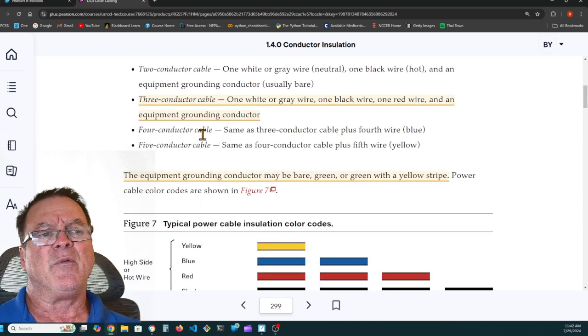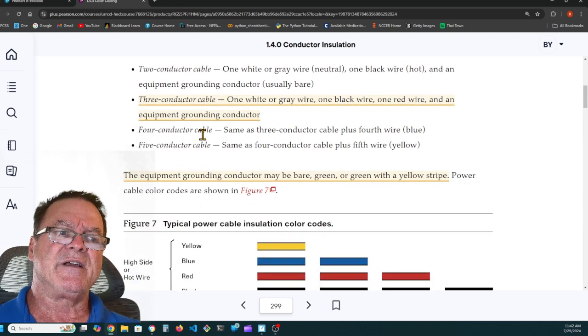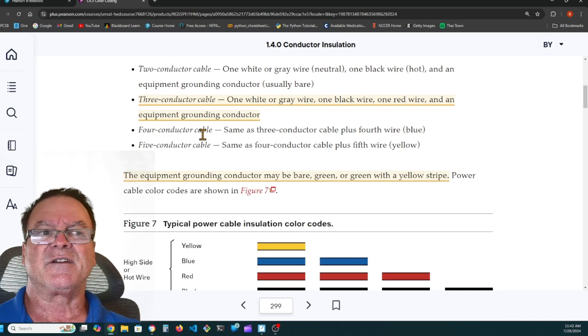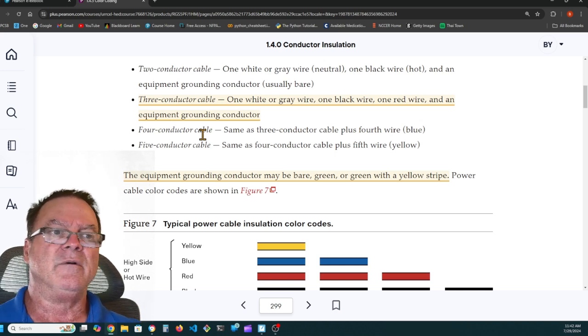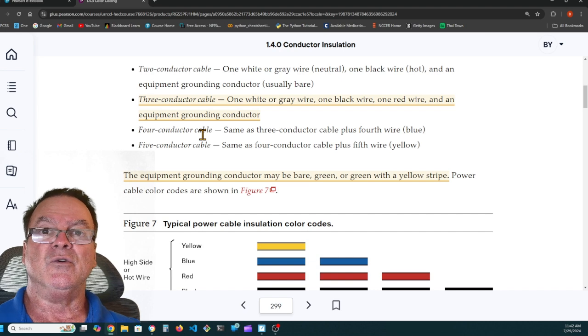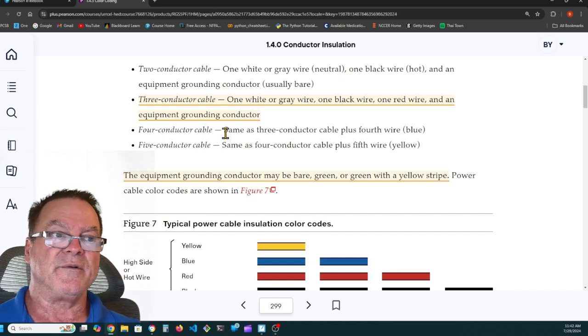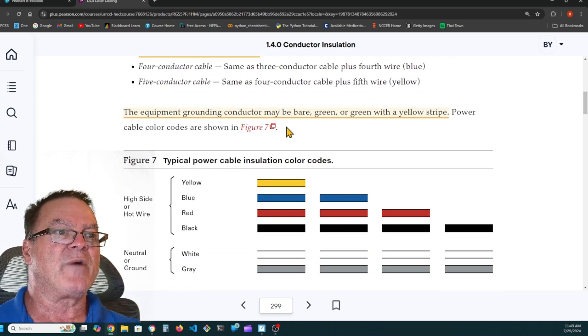4 conductor cable, you won't see this in residential because they say it's a 3-phase conductor or cable. It's black, red, blue, white, and ground. So same as 3 conductor cable plus a 4th wire, blue. 5 conductors, same as the 4 conductor cable plus a 5th wire, yellow. Here's a highlight. It says the equipment grounding conductor may be bare, green, or green with a yellow stripe.